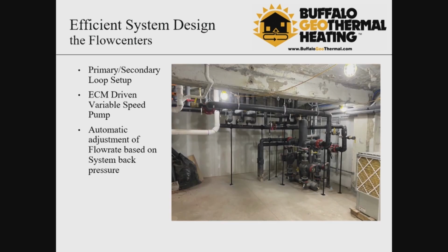On the north side, which will house the future restaurant, we opted to go with a primary secondary loop flow center. This way, the loop field loop and the house loop are decoupled from each other, and we can independently transfer heat from the individual heat pumps in the house to others, enabling us to use the excess heat of the future restaurant in early and late winter months to transfer directly to the apartment heat pumps to heat those instead of having to pump through the loop field.